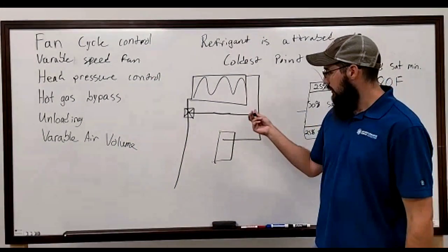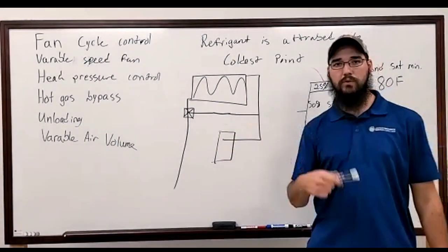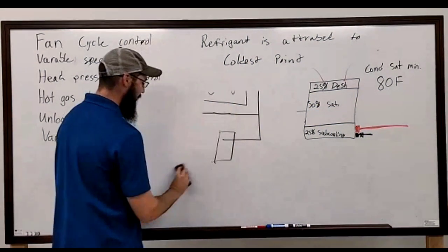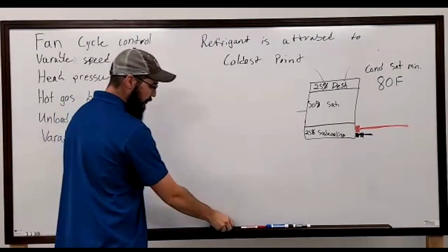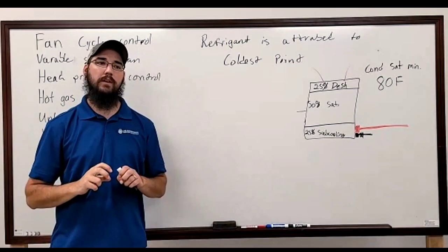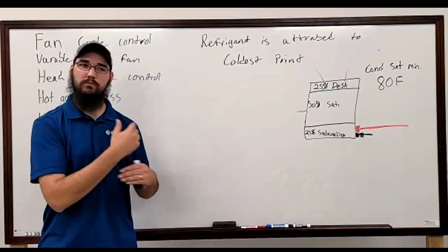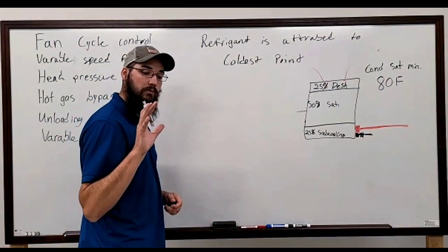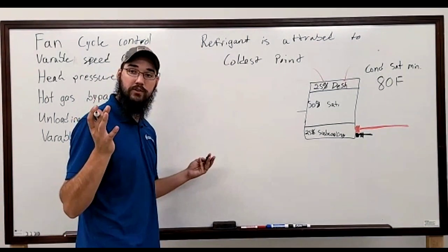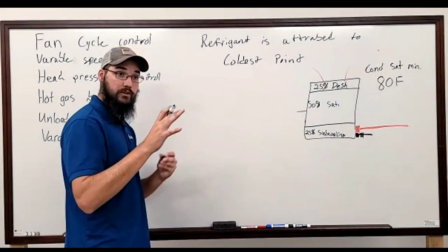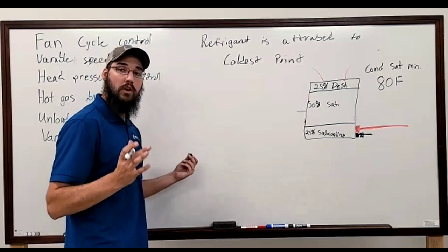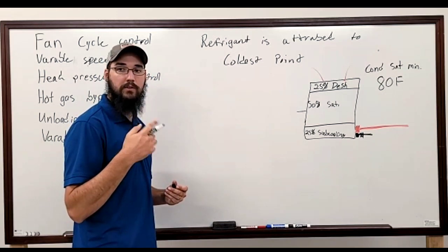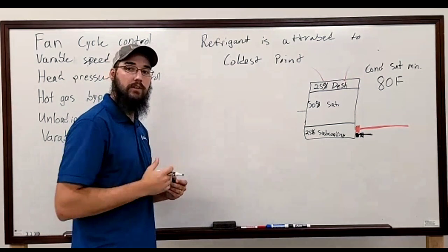As I said earlier, you'll have a pipe going from your discharge over to the two-phase line of your evaporator. This has less to do with condenser and temperature control, more to do with evaporator control, but it all kind of works together. You'll see these on many rooftop units that have some sort of dehumidification control or reheat. It's very, very common to use these. Most all of your outside air units will have some version of this. Aaon and Daikin Rebel systems will have a hot gas bypass valve that is an EXV typically.